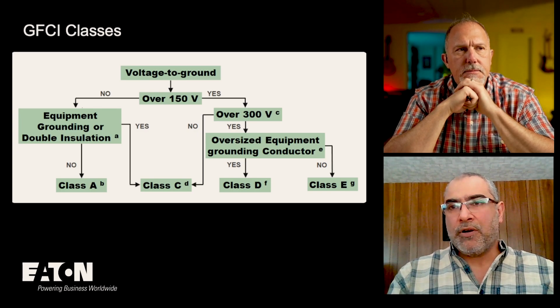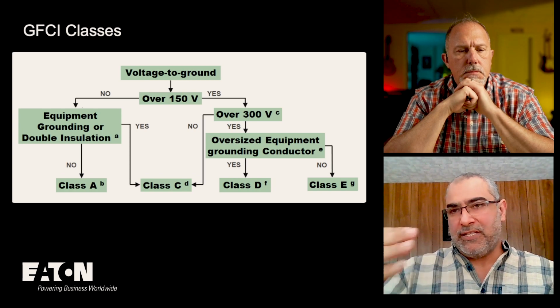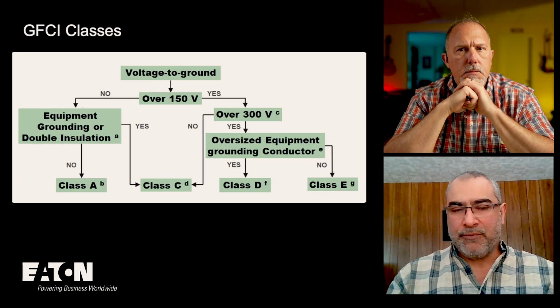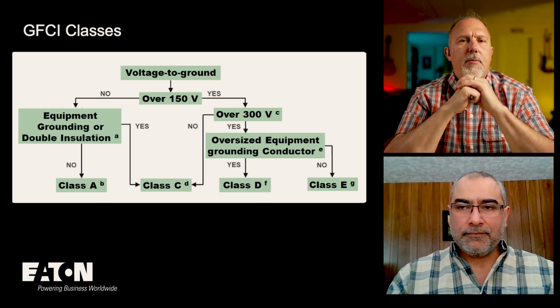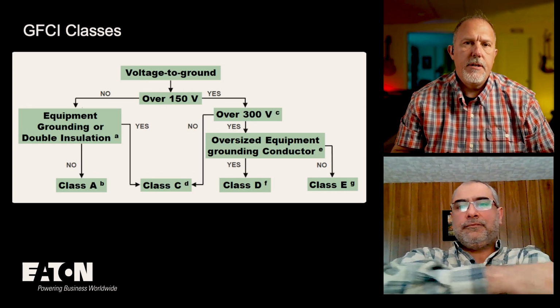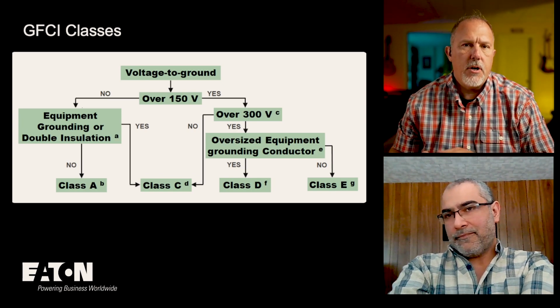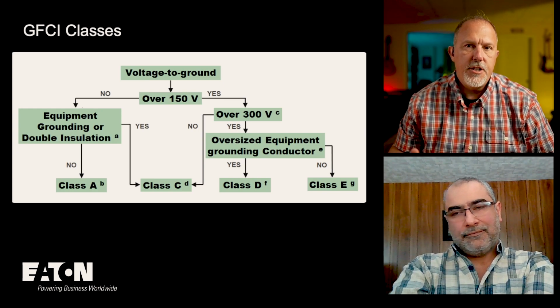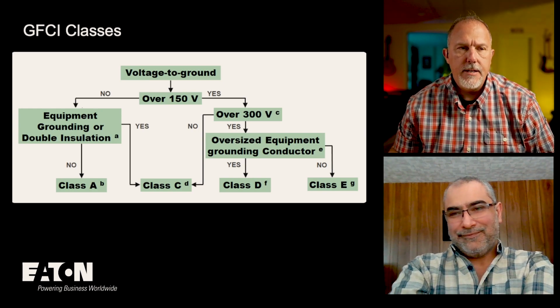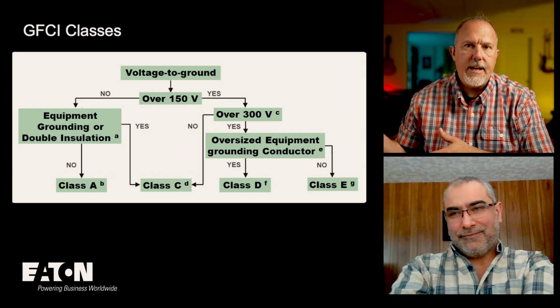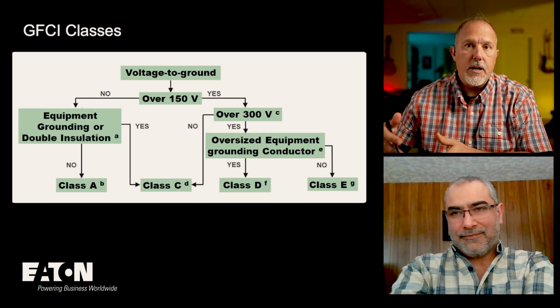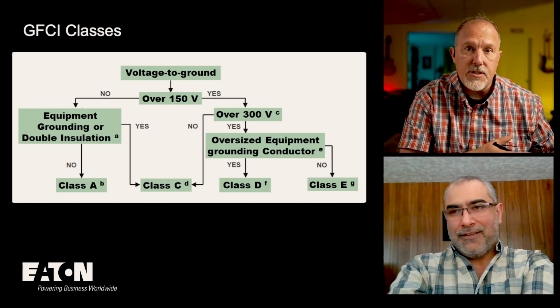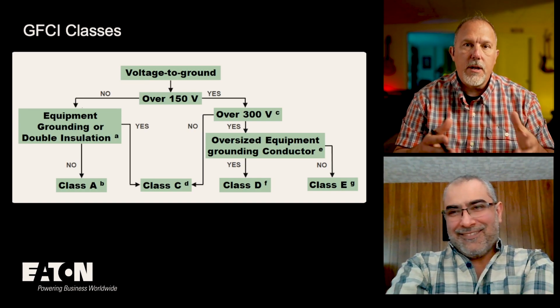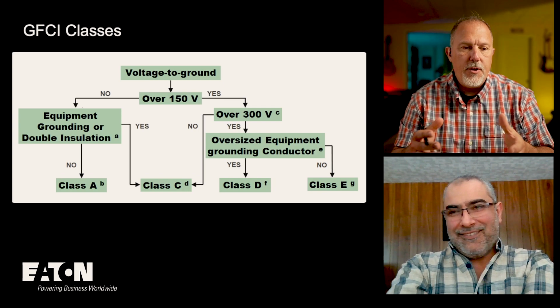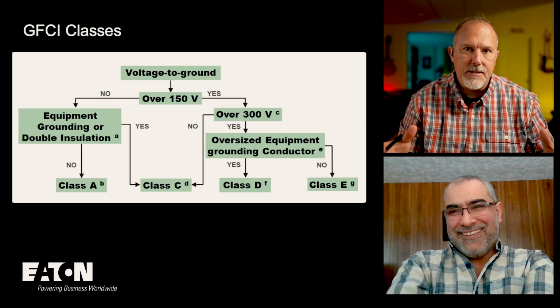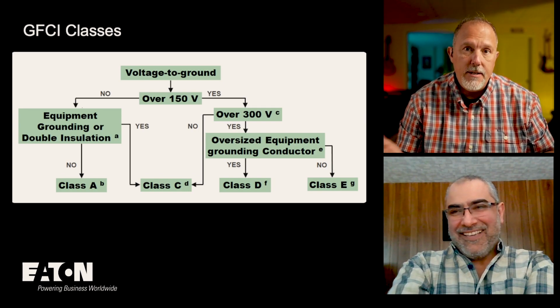They can be used anywhere, depending on what the code requires, like Class A. It's almost as if it would have been better if the National Electrical Code called it a Class C GFCI, Class D GFCI, and then specifically say a Class C is permitted, a Class D is permitted, or a Class A is required. If you stuck with the classes, it would probably make more sense, wouldn't it?